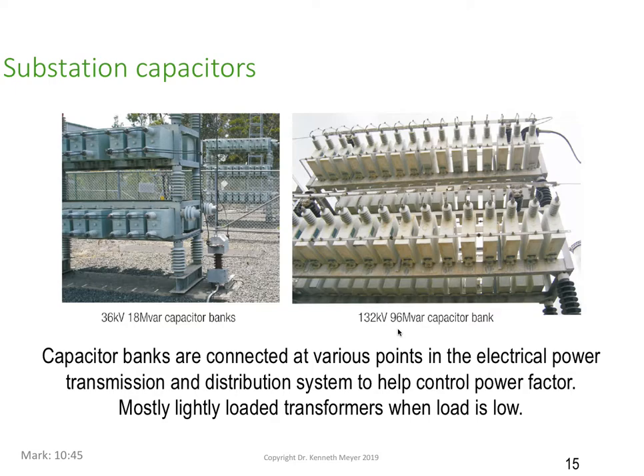On the right hand side, similar thing again, but this is 132 kV, so very, very high voltage capacitor bank at 96 MVAR, so very, very high amounts of capacitors being used to bring the power factor back on the system. So capacitor banks are used at various points in the electrical power distribution system to help control power factor, mostly lightly loaded transformers. So the transformers tend to get lightly loaded at night or on cooler days when no one's running their air conditioning systems. So when the load goes light, supply authorities will often switch in these capacitor banks.